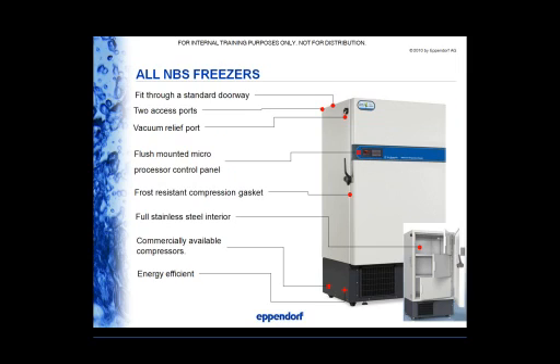And finally, just to summarize, some unique features about the New Brunswick freezers is that, well, every single one of our freezers will fit through a standard doorway. This includes upright and chest freezers, giving you the ability to put freezers inside your lab space. Every freezer is equipped with 2 accessory ports. Can be used for monitoring devices as well as backup systems. Vacuum relief port with ice plunger. This is a unique feature to release the vacuum anytime that you need immediate access to the freezer. All of our controllers are flush mounted with microprocessors positioned at eye level for easier reading, and they can easily be set up with password protection.